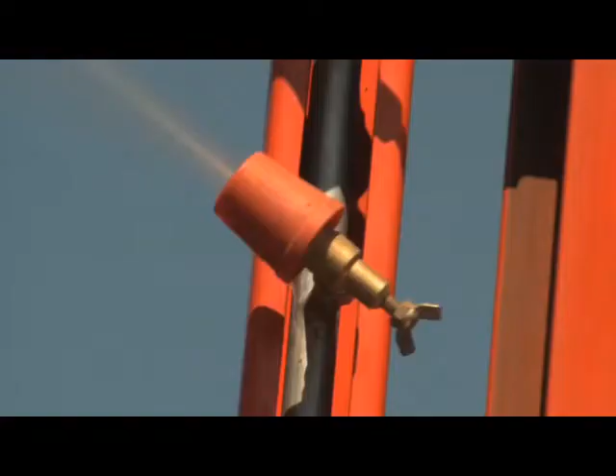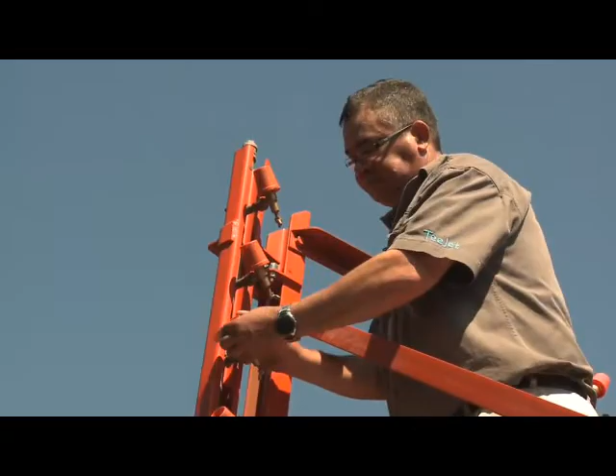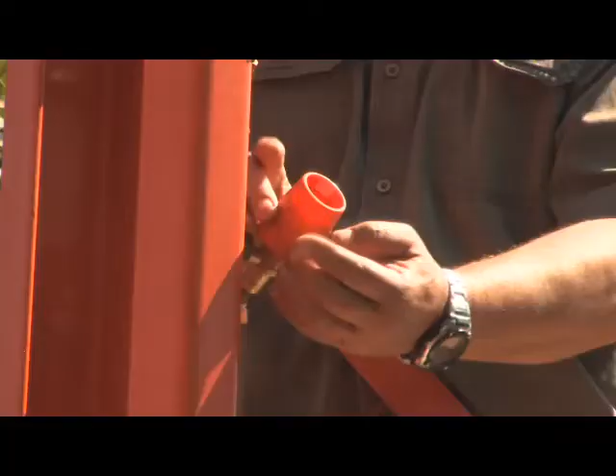So we found that the third nozzle from the top was partially blocked, and I'm going to show you how to clean this nozzle. You have to unscrew the nozzle and you have to clean it under pressure. And shut this valve down completely. And then you screw the cap back on. And there you adjust it. So this nozzle is now ready for spraying.